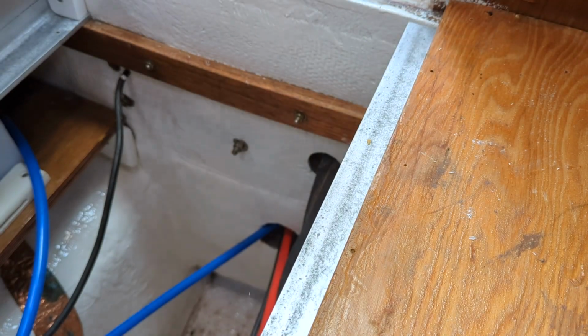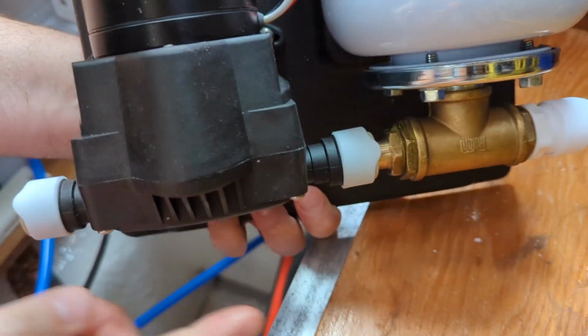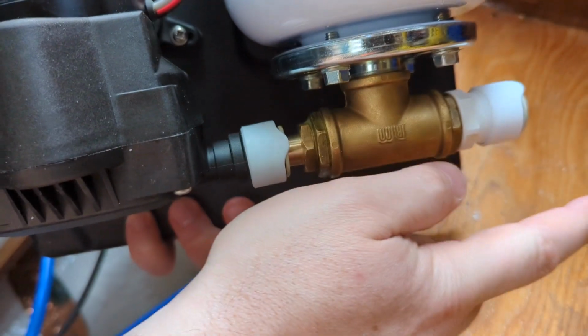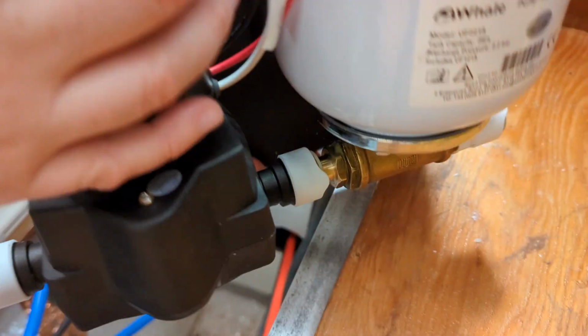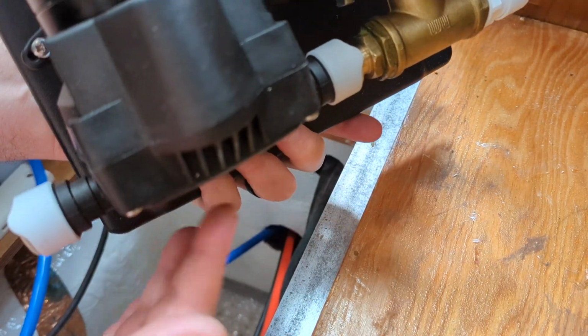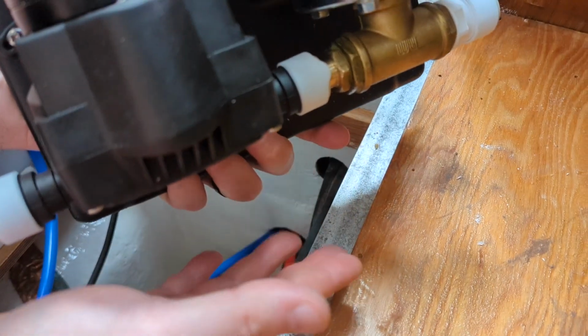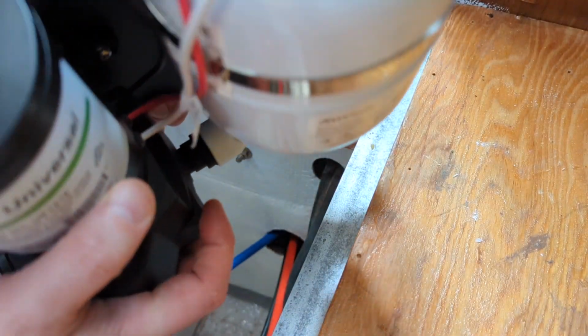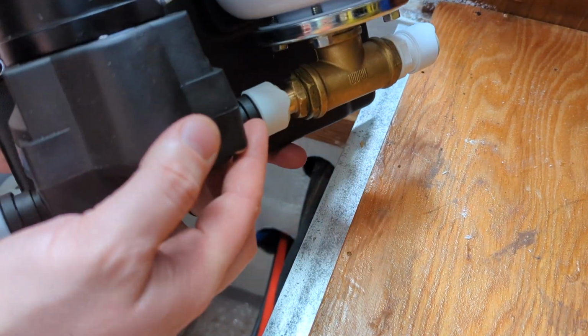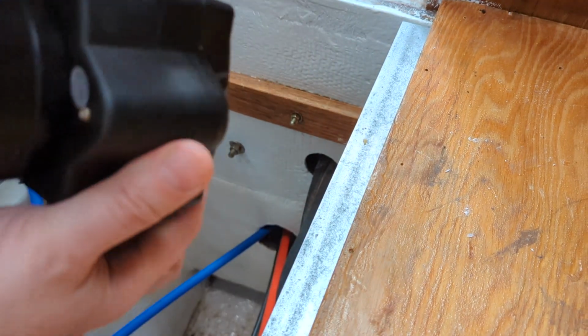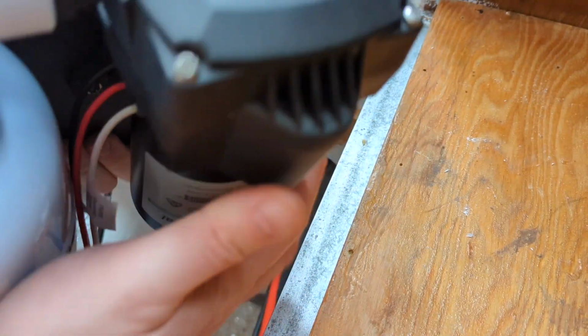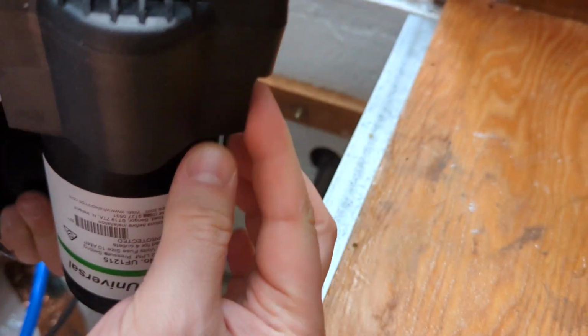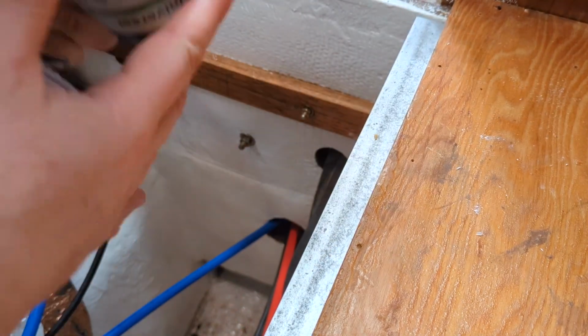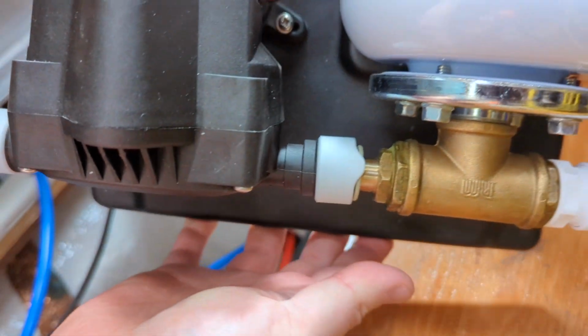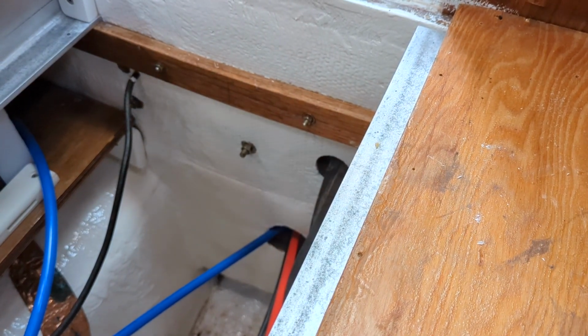Notice here that your water passes through and goes out as you use it, while your electric pump is up top. So if you spring a leak in these fittings, which will probably happen at some point, the water will drip down and away from your electrics, pump housing, and pump head. If you had it oriented the other way and sprang a leak at the fittings, it could drip down into your pump. So we want to follow their recommended guidance to have it oriented like that.